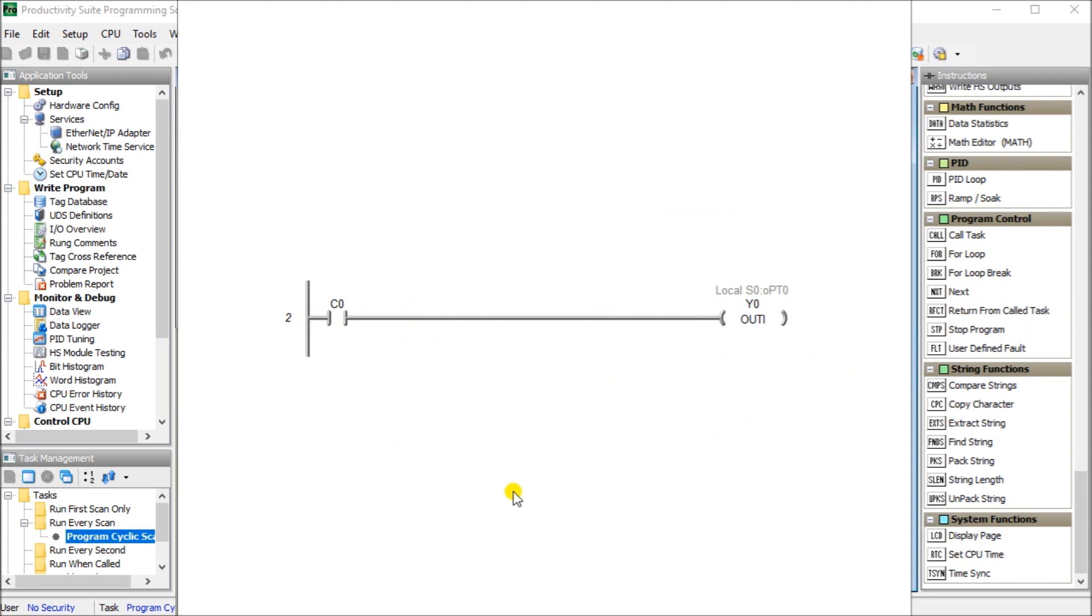Depending on the controller used, an immediate output can be used to change the physical output within the program scan. Here is an example of the Productivity PLC and it has an out I, which is out immediately. So during that scan, when this is energized, it actually will send that output immediately to the physical IO.